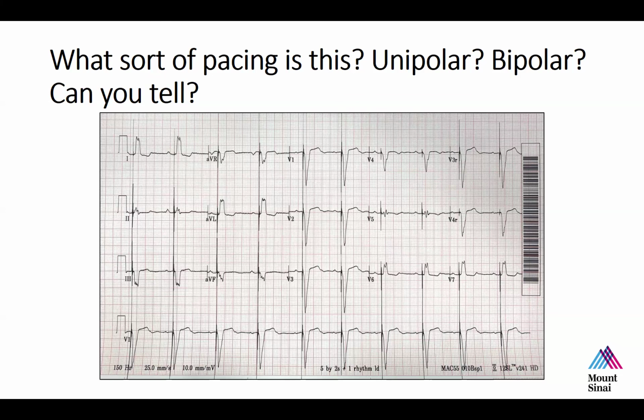The only cases where we see it, in my experience in the present era, is sometimes some surgeons will put unipolar button electrodes on the heart of small infants because they don't want to put a bipolar lead on because there's only so much real estate on the epicardium of a small baby. And so they sometimes are paced unipolar, although most surgeons have moved to putting bipolar epicardial leads.